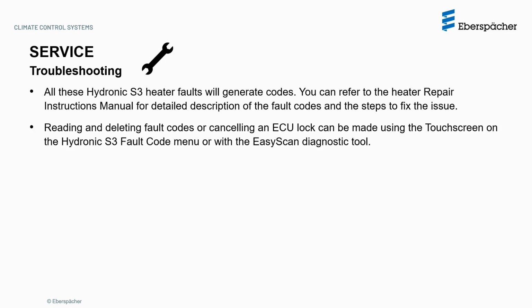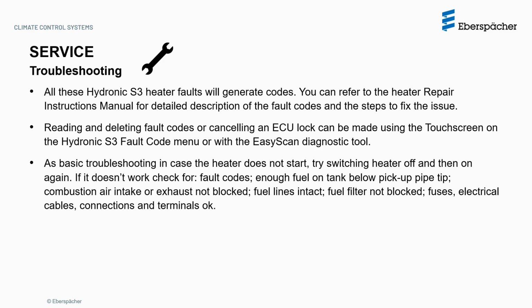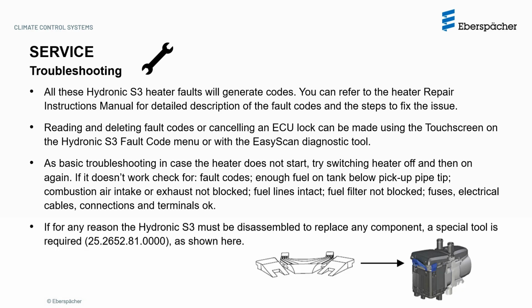Reading and deleting fault codes or cancelling an ECU lock can be made using the touchscreen on the Hydronic S3 fault code menu, or with the EasyScan diagnostic tool. As basic troubleshooting, in case the heater does not start, try switching the heater off and then on again. If it doesn't work, check for fault codes, enough fuel on the tank below pickup pipe tip, combustion air intake or exhaust not blocked, fuel lines intact, fuel filter not blocked, fuses, electrical cables, connections, and terminals OK. If for any reason the Hydronic S3 heater must be disassembled to replace any component, a special tool is required. The tool part number and image is shown here.